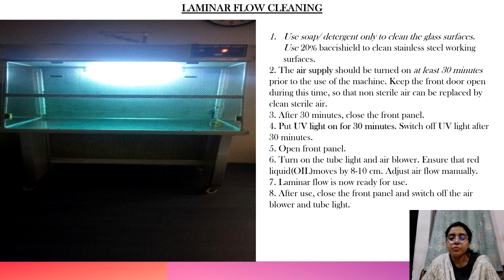The air supply should be turned on at least 30 minutes prior to the use of the machine. Keep the front door open during this time so that non-sterile air can be replaced by clean sterile air. After 30 minutes, close the front panel. Put the UV light on for 30 minutes. Switch off the UV light after 30 minutes. Open the front panel. Turn on the tube light and air blower.